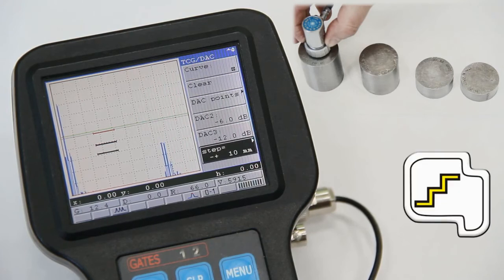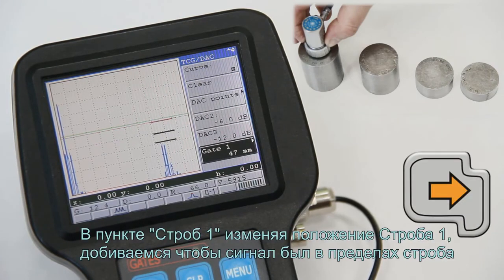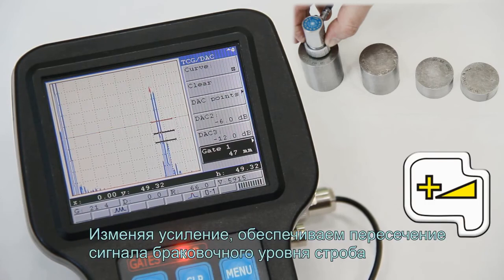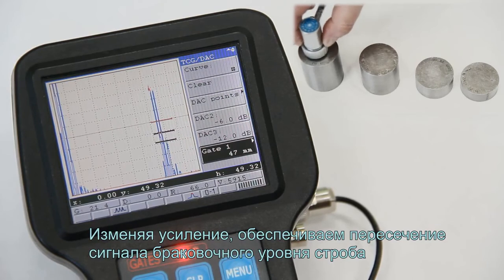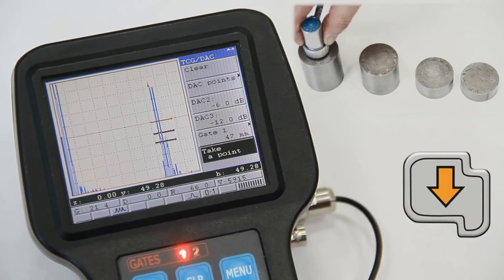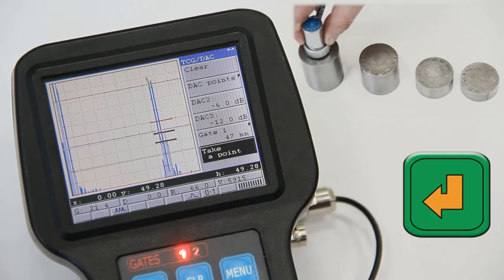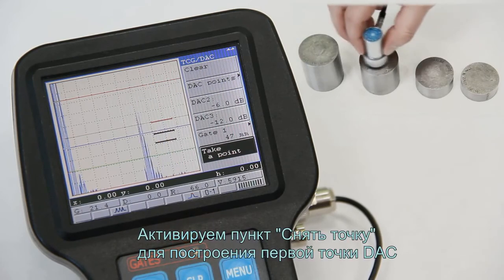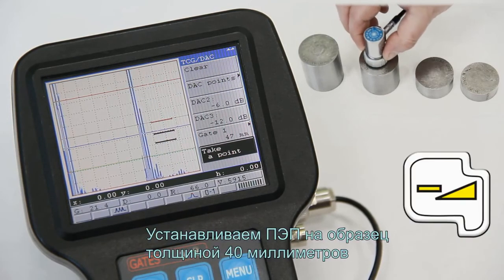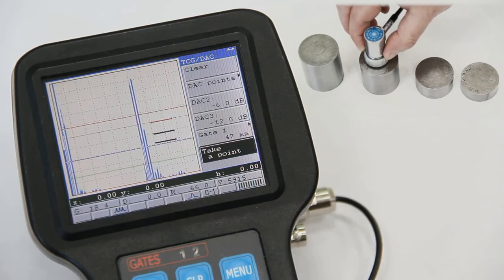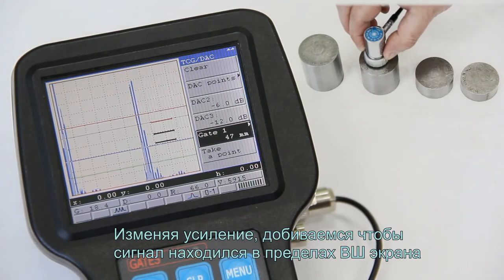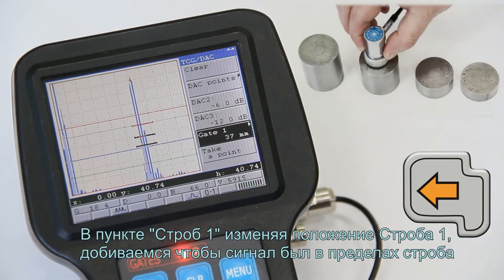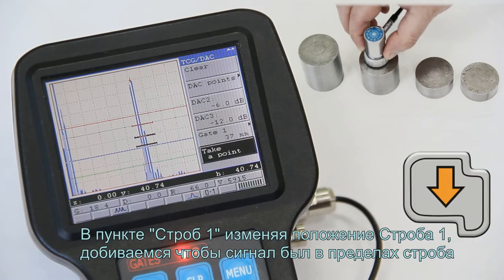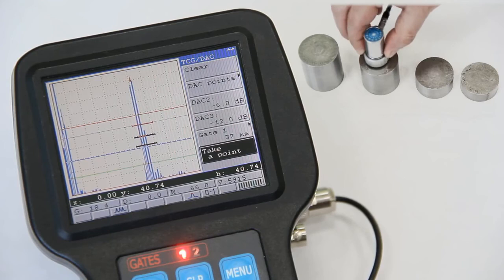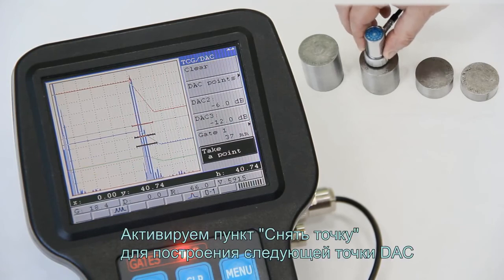In gate 1 item, achieve the signal to be within the gate by changing the position for gate 1. By changing the gain, ensure the signal of acceptance gate level to be crossed. Activate the Take a Point item to plot the first DAC point. Place the probe at 40 mm thickness block. By changing the gain, achieve the signal to be within the screen vertical scale. In gate 1 item, achieve the signal to be within the gate by changing the gate 1 position. Activate the Take a Point item to plot the next DAC curve point.